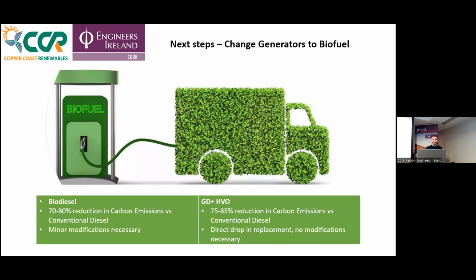I've been asked a couple of times recently by developers about needing the redundancy of a traditional diesel generator or large-scale batteries to provide backup for sites being built in Dublin - they're very expensive, and they need explosion-proof rooms and all this good stuff. These days you can install diesel generators and just run them on HVO. So it means you can still provide a green solution to your clients with a diesel generator. There's no modification required for Cummins or any of those newer type generators - most are built to take dual fuel. So it's just another consideration people can have when designing new buildings that need a UPS system. You mightn't actually need 2 ESB incomers for redundancy - you can get away with other solutions if you just know the technology that's there.